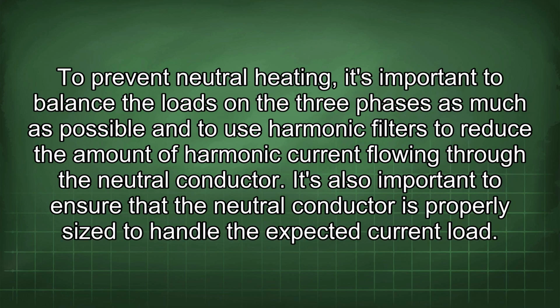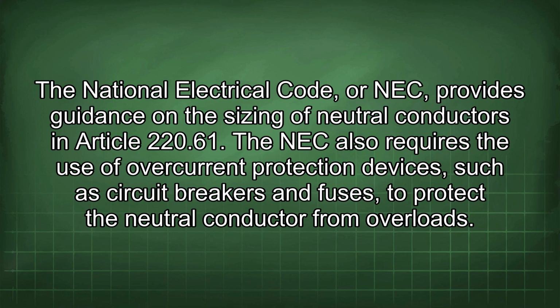To prevent neutral heating, it's important to balance the loads on the three phases as much as possible and to use harmonic filters to reduce the amount of harmonic current flowing through the neutral conductor. It's also important to ensure that the neutral conductor is properly sized to handle the expected current load. The National Electrical Code, or NEC, provides guidance on the sizing of neutral conductors in Article 220.61. The NEC also requires the use of overcurrent protection devices, such as circuit breakers and fuses, to protect the neutral conductor from overloads.